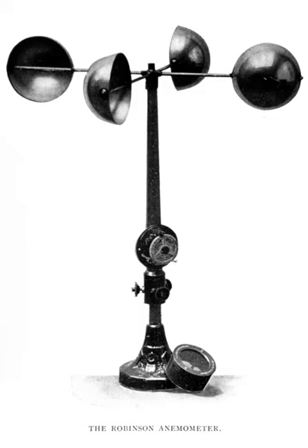One of the other forms of mechanical velocity anemometer is the vane anemometer, also described as a windmill or propeller anemometer. Unlike the Robinson anemometer, whose axis of rotation is vertical, the vane anemometer must have its axis parallel to the direction of the wind and therefore horizontal. Since the wind varies in direction and the axis has to follow its changes, a wind vane or other contrivance must be employed. A vane anemometer thus combines a propeller and a tail on the same axis to obtain accurate wind speed and direction measurements. The speed of the fan is measured by a rev counter and converted to a wind speed by an electronic chip, and volumetric flow rate may be calculated if the cross-sectional area is known.